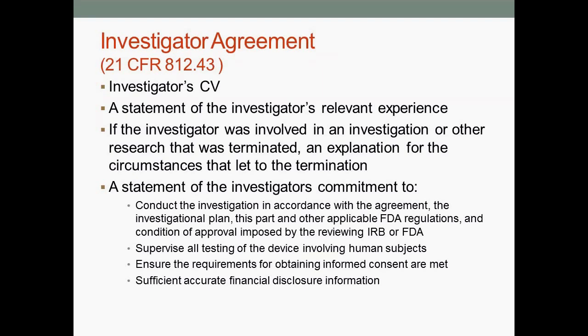investigator's commitment, so that they are willing to conduct the investigation in accordance with the FDA regulations, that they're going to supervise all the testing of the device involving human subjects, they're going to ensure the requirements for obtaining consent are met, and that sufficient, accurate financial disclosure information is given. So that's very basic, and that's in a lot of your investigator agreements. However, there are sponsors that tend to elaborate on that, and you could end up with a one-page investigator agreement, or you could end up with a four-page investigator agreement.